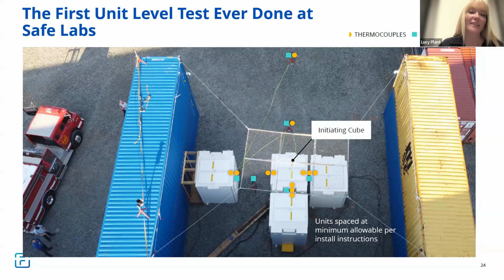The next slide just shows some of the thermocouples we have. When we're doing these tests, we're getting as much data as we can. We have a gas collection above the system itself, so all the gases that come off, we're collecting those. We understand from the cell level, but you're going to have additional combustible material within that enclosure, and we want to understand what gases that produces. Again, so we can use that for education for first responders, for environmental impact assessments, and for after-the-effect reviewing how we control and clean up if one of these events occurs at one of our sites, and then for community engagement.